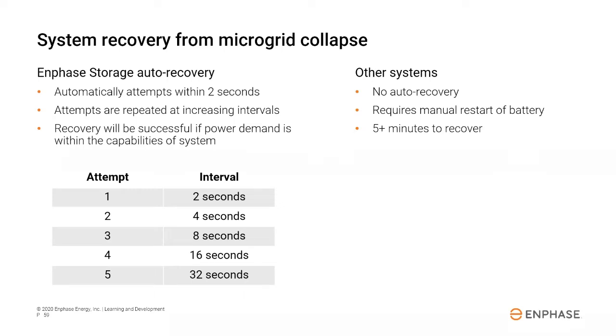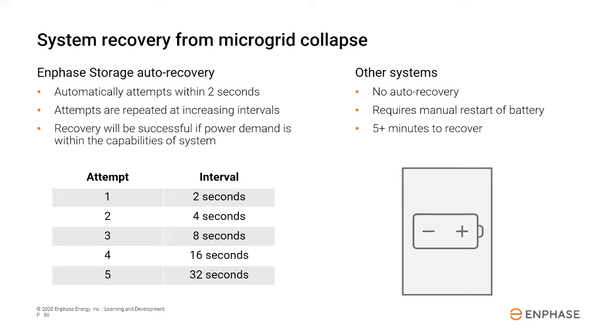This approach works because often the appliance which caused the overload will be off and won't restart immediately when the power is restored. Rapid system recovery turns the lights back on quickly so that the owner can easily resolve the issue by turning off circuit breakers to large loads or turning off the thermostat. Typical battery storage systems don't have an auto recovery capability. If they shut down due to a microgrid collapse, they must be manually restarted, and the recovery takes 5 minutes or more.